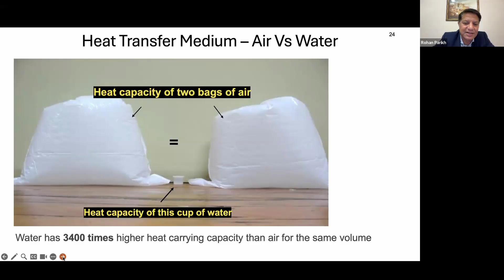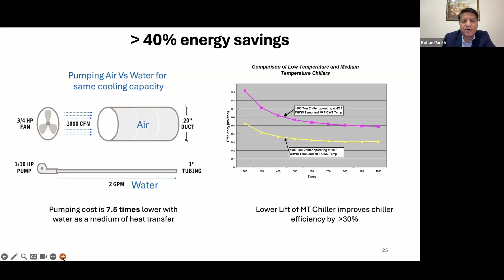For air conditioning in India we normally have to cool water down to 7 degrees, but with radiant cooling only to 16 degrees. For every 1 degree less you need to cool, that lift reduction gives you 2 to 3% savings. So the combination of pumping energy and chiller energy savings was more than 40%, which I spoke about.